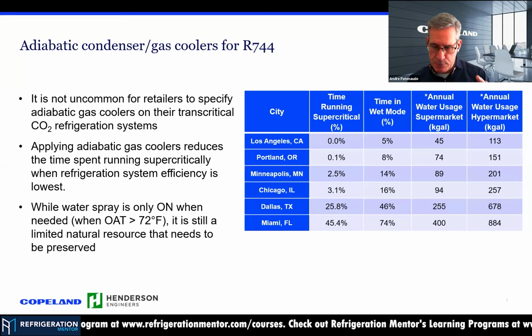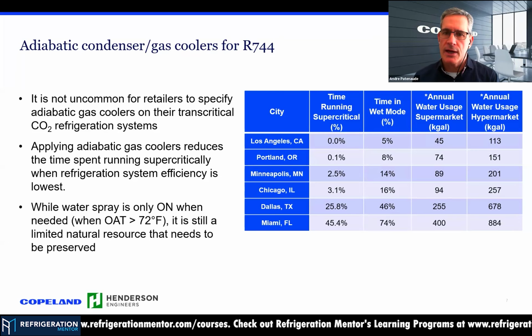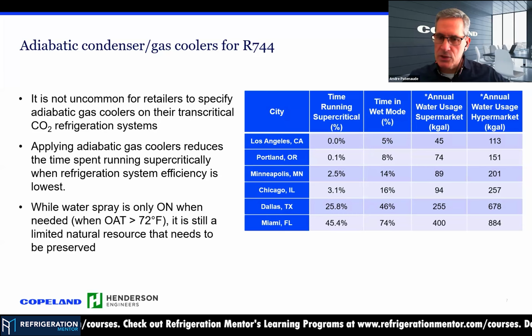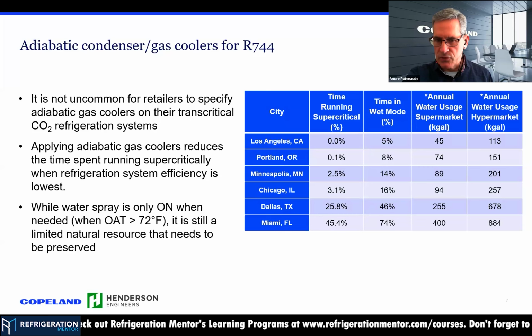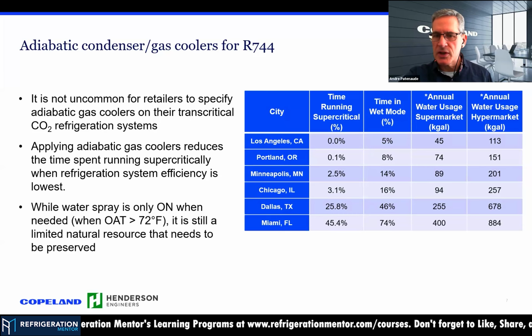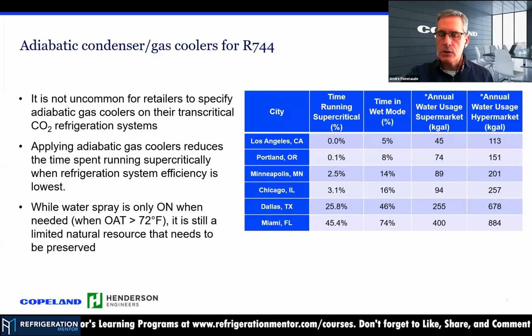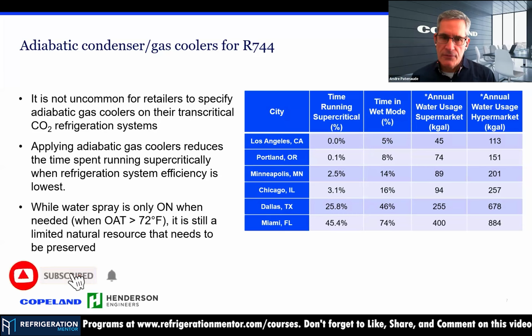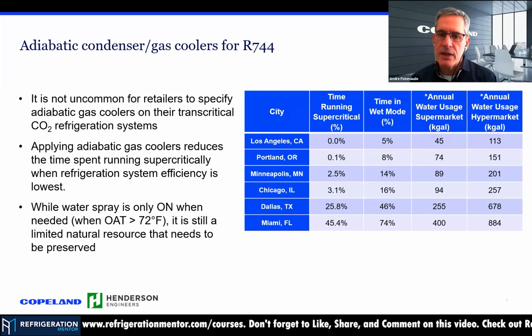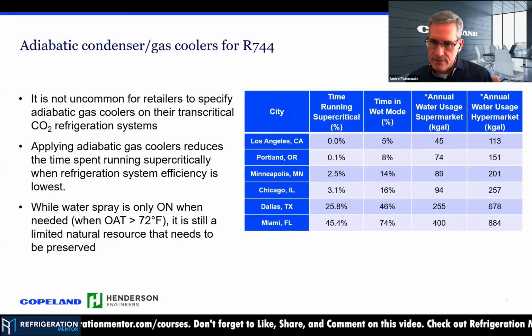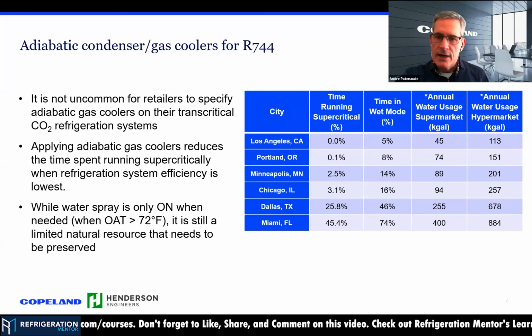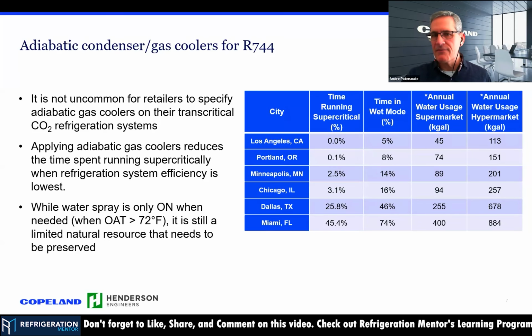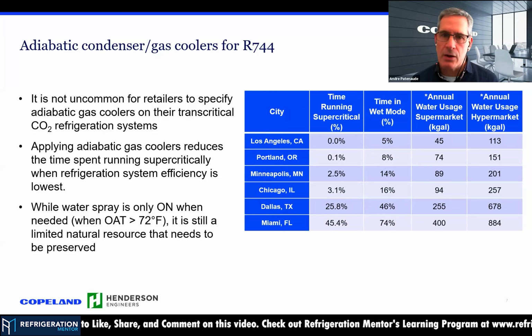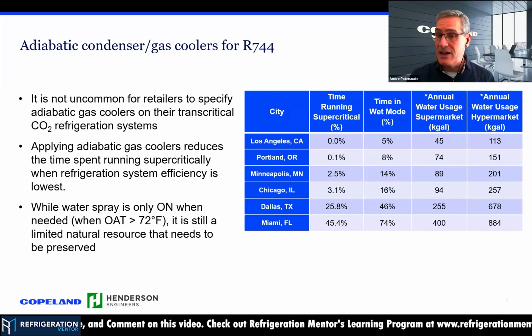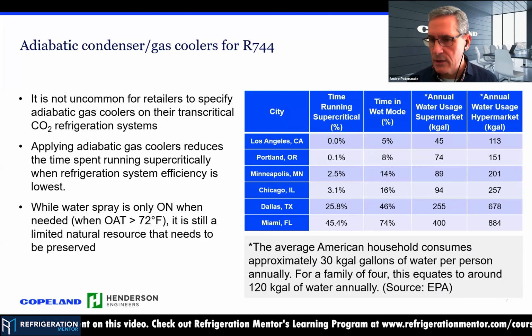Applying adiabatic in this particular study, we turn the water on at anything over 72-degree ambient. The water would start to trickle onto these pads. And what's interesting, when you look at Los Angeles all the way down to Miami, the percent runtime in supercritical using weather data from NREL, National Renewable Energy Labs, TMY3 - this is the temperature data we used - showed that the water only came on 5% of the year, out of 8,760 hours a year. And it used 45,000 gallons for a supermarket and 113,000 gallons for a hypermarket.